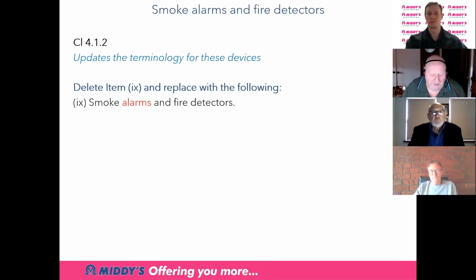Okay, as Gary mentioned before, throughout the document we have removed or amended the fire detector or smoke detector clause. A smoke detector usually sends a signal to a fire alarm panel. That was never the intent of the clauses. The clauses were that there were smoke alarms, as you have in your home and in many commercial and non-residential situations, where we actually referred to the smoke alarm itself. So a smoke alarm is a self-contained unit that will actually go off, and it's been modified now. So we now include smoke alarms and the smoke detectors that feed back into the board. Next slide, please.